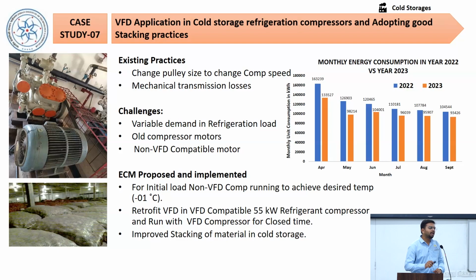At other times, they only have to use the VFD compressor. Once the temperature is achieved in the system, since the cold storage is heavily insulated all over, with the VFD application they can also maintain a lesser refrigerant requirement. So the industry, between before 2022 and after 2023, is getting around 25,000 units of savings per month from the implementation of this VFD. And they recovered the VFD cost in almost 3 to 4 months. So that is a significant energy reduction in cold storage.